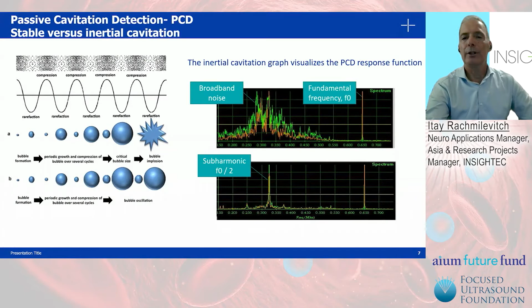of the treatment. What we can see here is actually our transducer. You can see here, of course, the matching layer with the tiles and the 8 detectors that are being placed on the transducer. Those detectors are actually configured in a fashion that is tuned to listen to half of the frequency, which proves so far to be effective over some thousands of treatments.